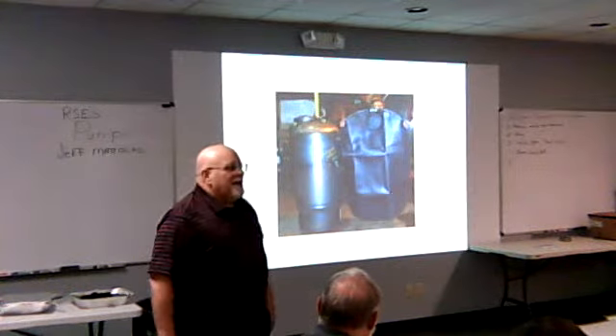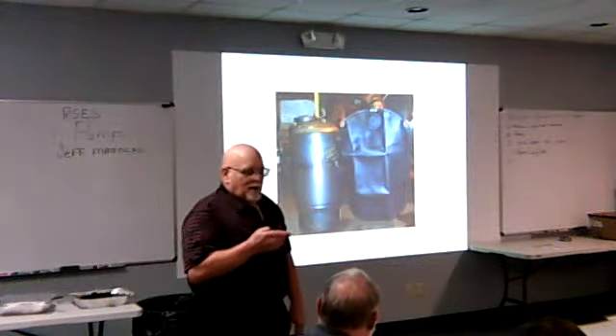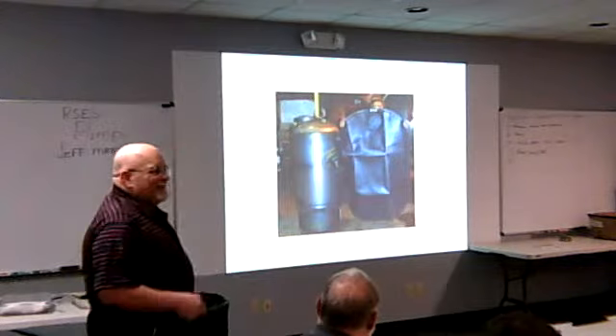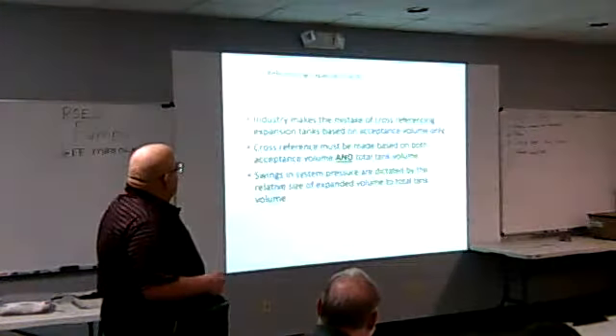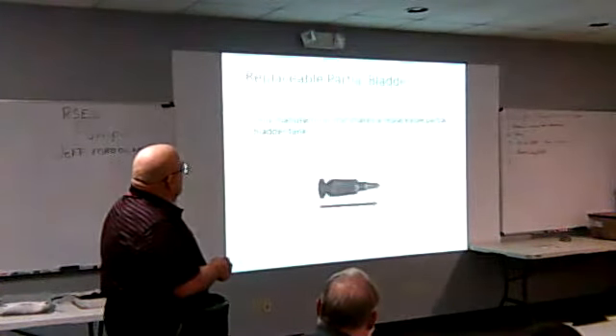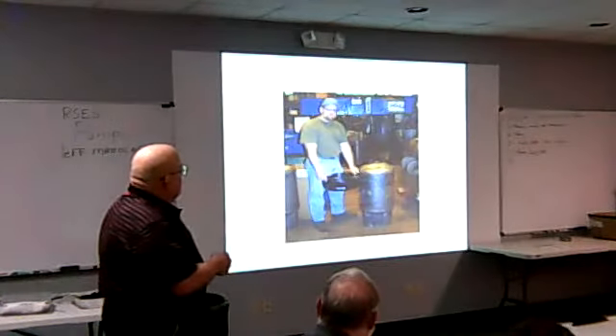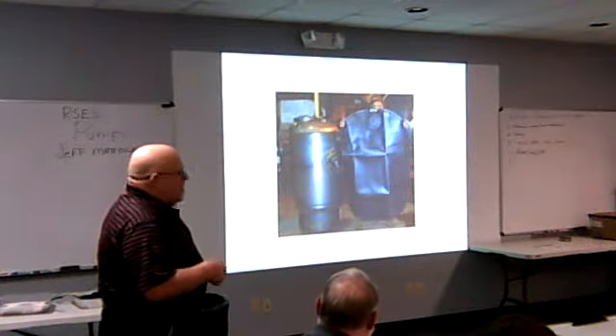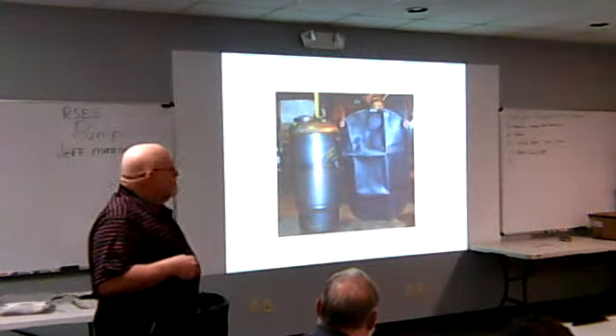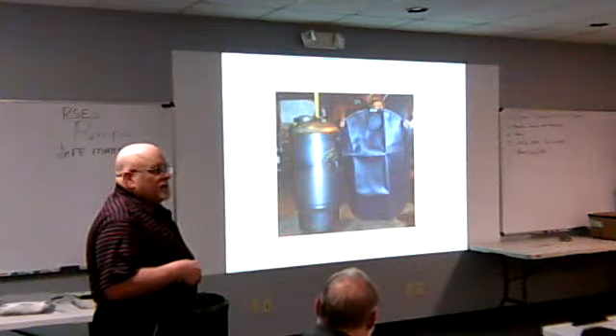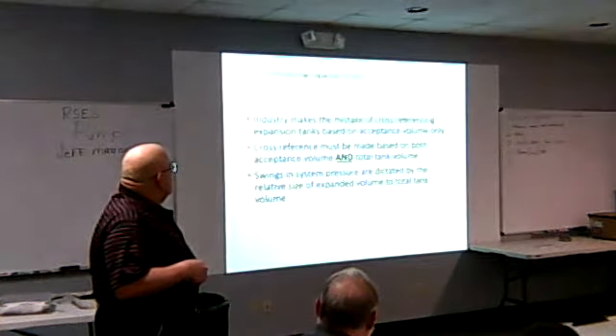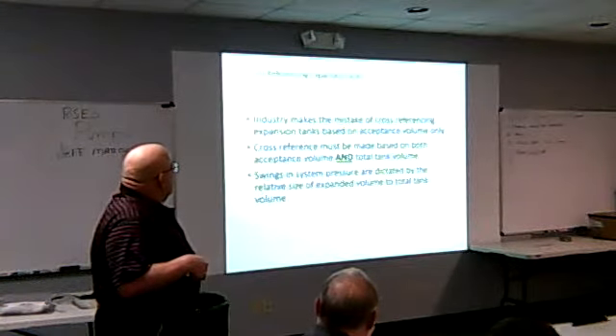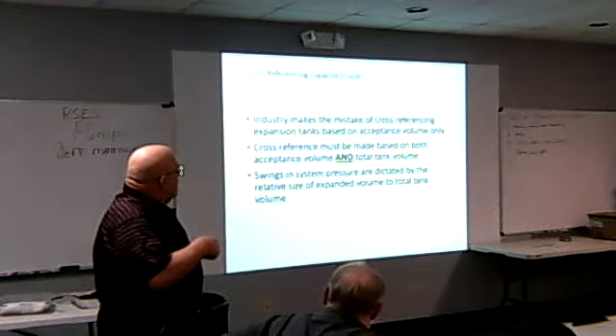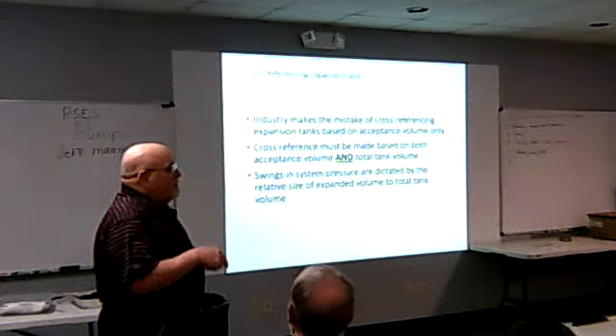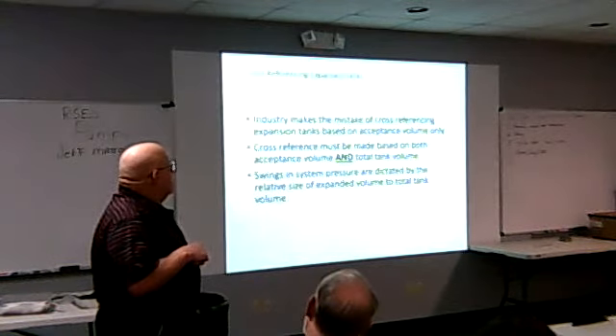Try getting it out of the water. It's a lot of work. So a lot of times people just opt to buy a new tank. But these bladders, it is acceptable to replace. This you can replace, this you cannot. All of our tanks are 125 pound ASME code. They're all ASME stamped and certified. Remember I said this is just telling you to look at that acceptance volume versus the full volume.